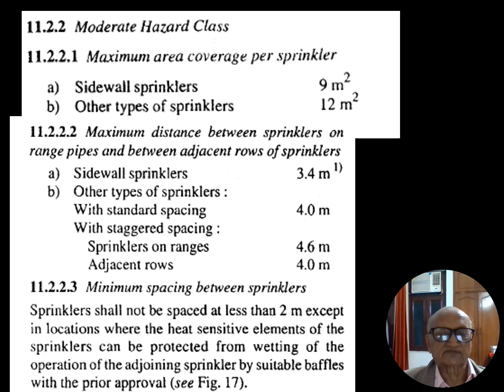Friends, with my experience of 35 years in CPWD, I would like to tell you that in most of the cases, more than 80%, these rules may be followed. It is on the safer side to treat a building like a hospital or business buildings with a moderate hazard class design, and in such areas side wall sprinklers shall be provided for every 9 square meter area or part thereof. Similarly, for other types of sprinkler, this is 12 square meter. So remember, every 12 square meter or part thereof, you are supposed to provide a sprinkler.